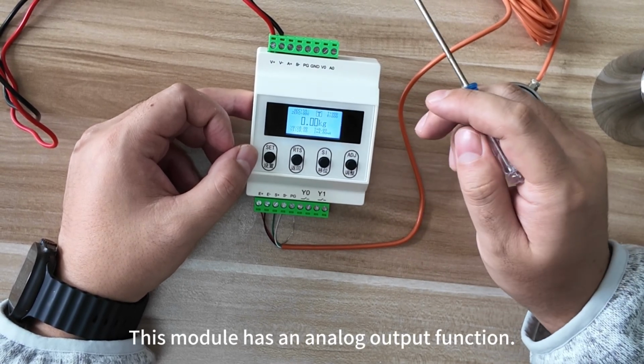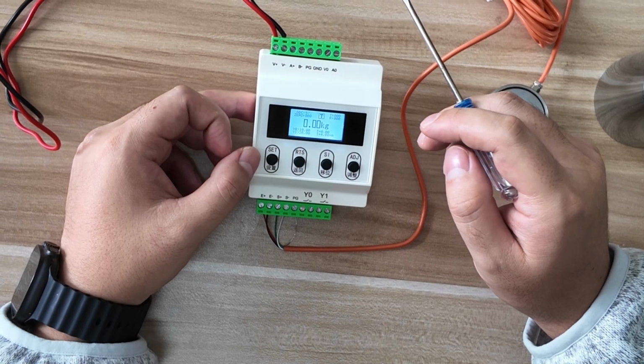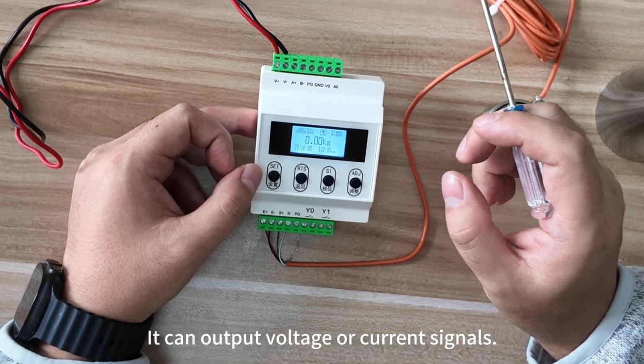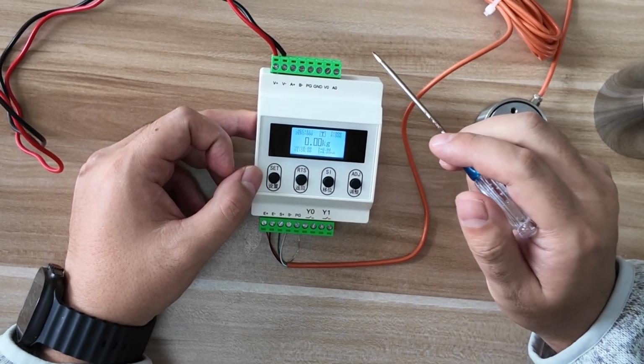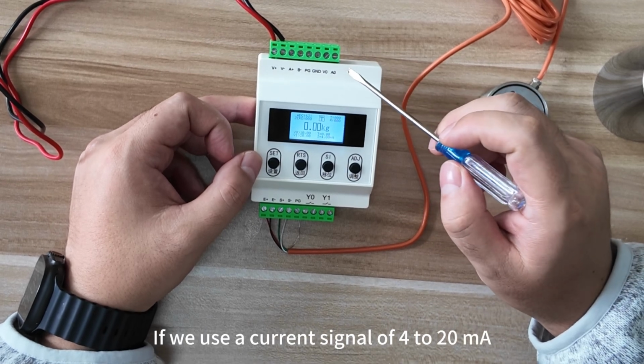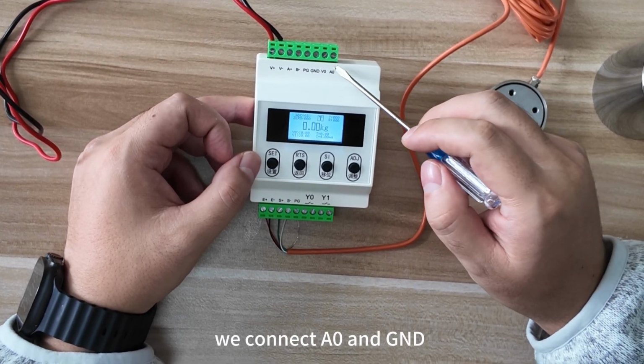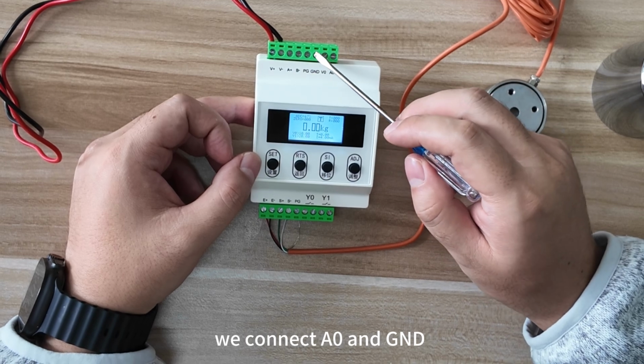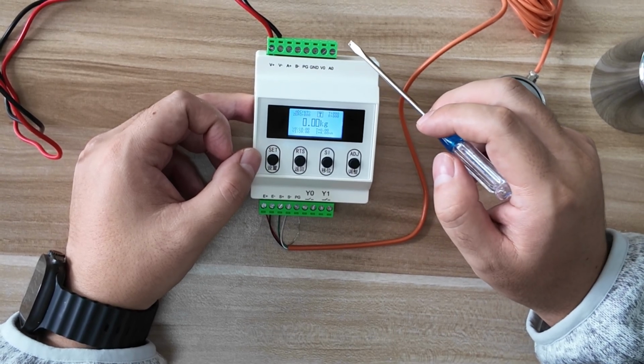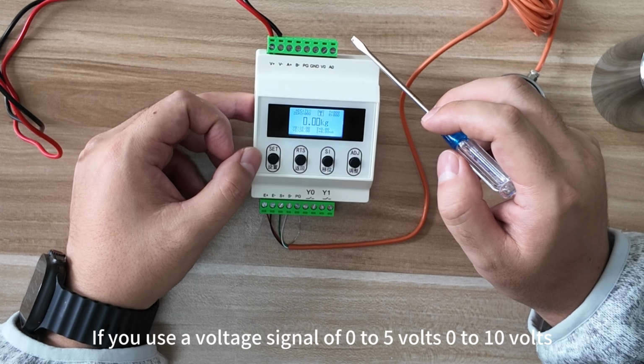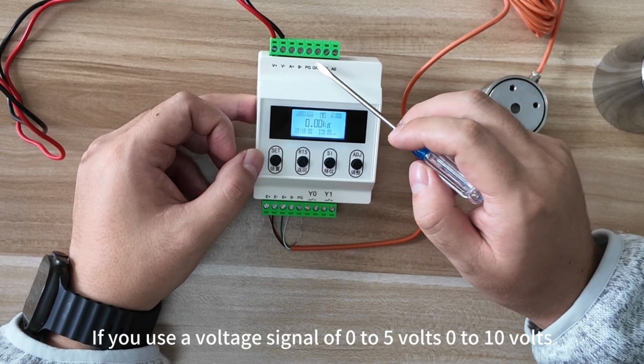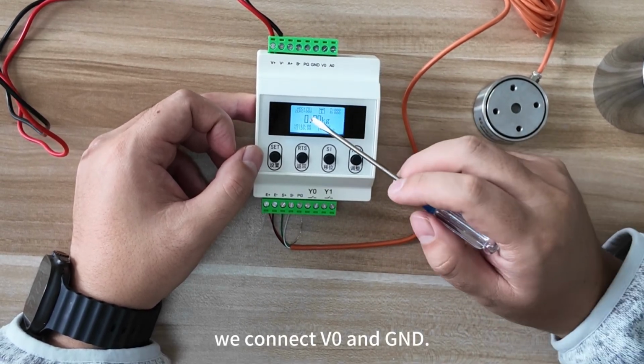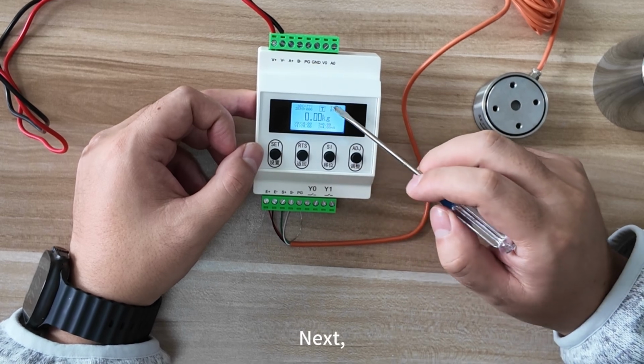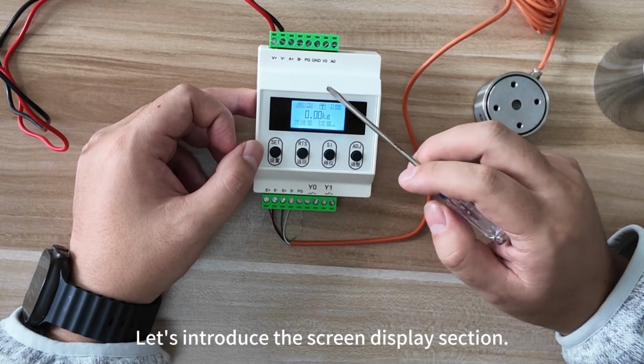This module has an analog output function. It can output voltage or current signals. If we use a current signal of 4 to 20 milliamperes, we connect A0 and GND to these two pins. If you use a voltage signal of 0 to 5 volts, 0 to 10 volts, we connect VO and GND. Next, let's introduce the screen display section.